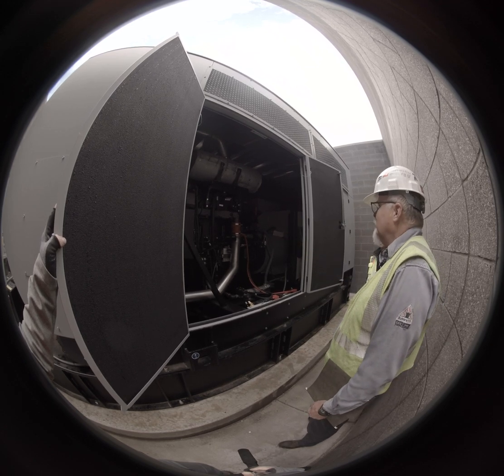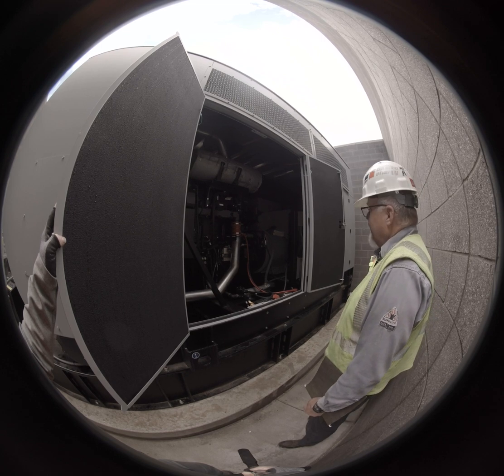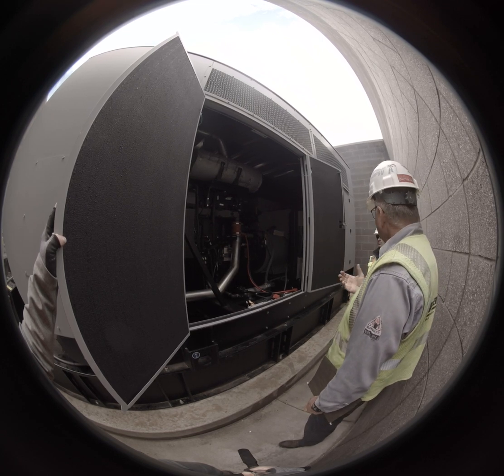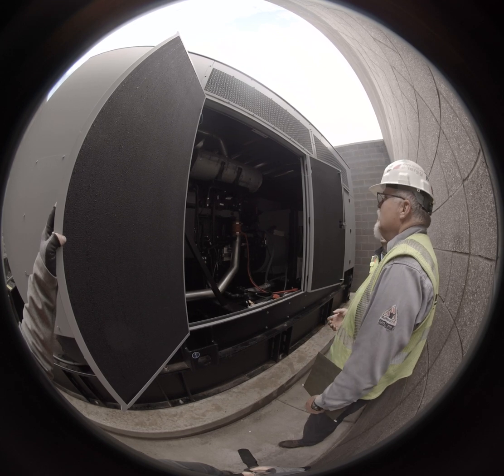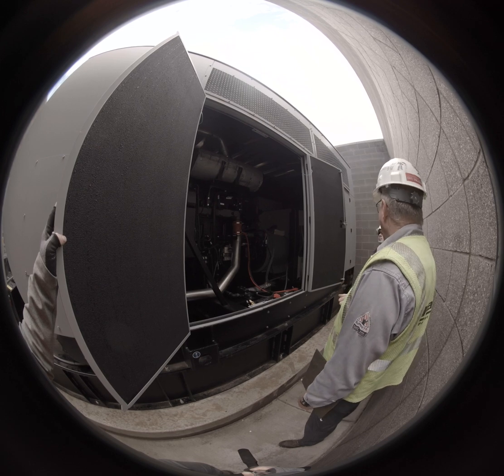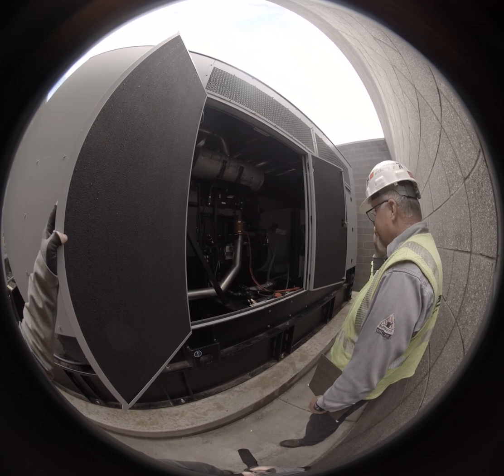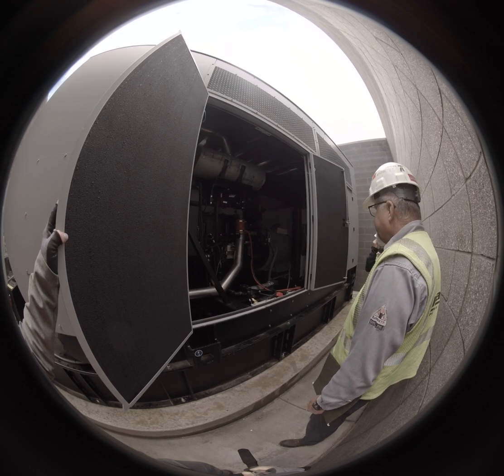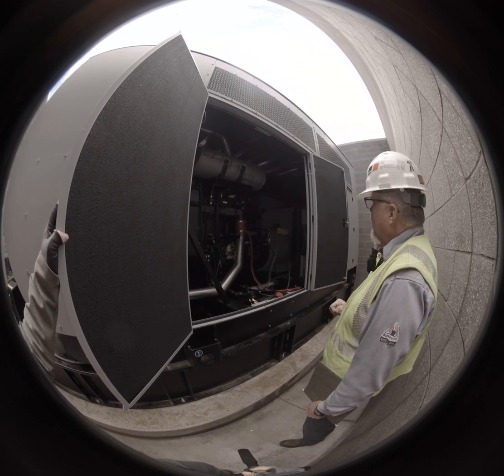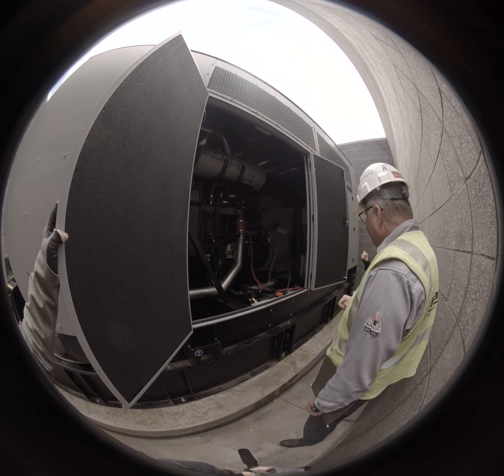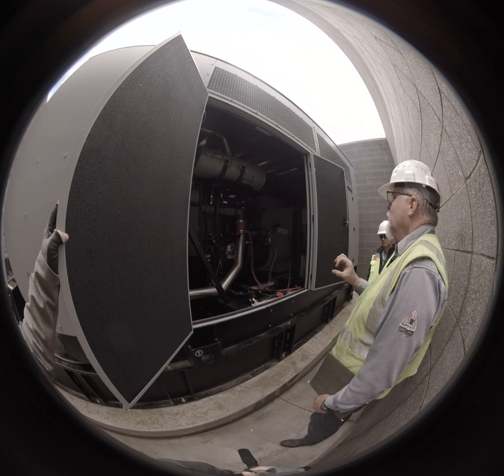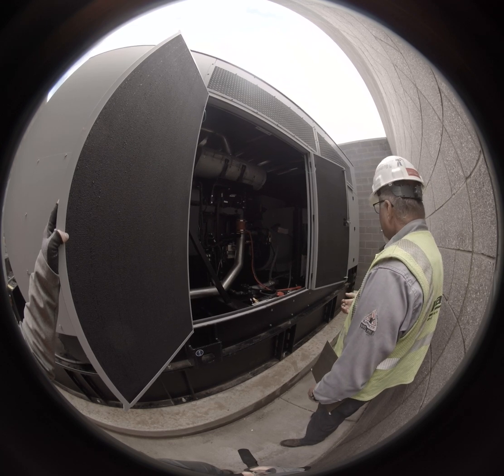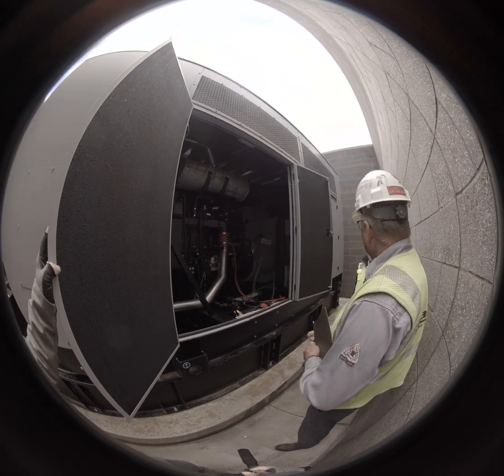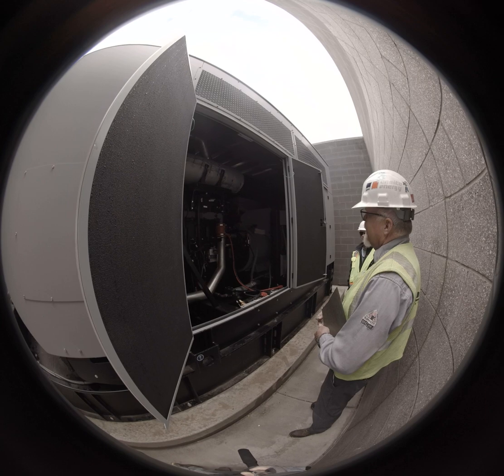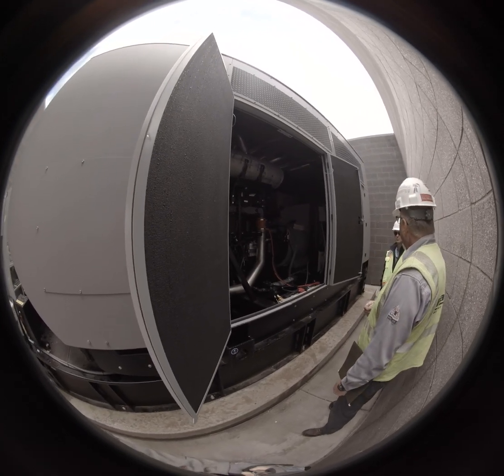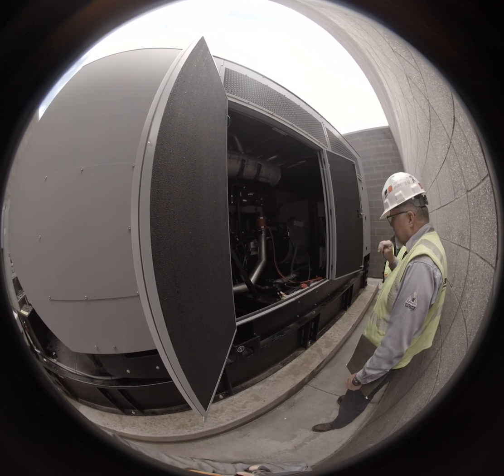Right underneath the charge air pipe there is the ECM for this engine. The ECM is monitoring multiple points around the engine, speed, temperatures, and pressures, to make sure that this engine runs up to optimum performance, emissions-wise, fuel economy-wise, and to pull the power. The ECM is talking directly to our control, which is through the next door, and with that, we do not run a second set of sensors on the engine. Old school engines, you had your high water temp shutdown, your high water temp pre-alarm, and your high water temp gauge. In this one, it's all done through the ECM, talking direct to the engine controls, or the genset controls.